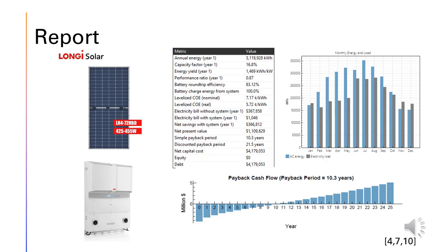From our simulations, we determined that the optimal configuration will be using the LONGi bifacial panels and the 208V ABB inverters. SAM provided us with a report of all the important metrics from our simulation. The LCOE of our proposed system is 7.17 cents per kilowatt hour, while the payback period is 10.3 years. We also used the graphs to ensure the generator power was sufficient for the electricity loads of the Bergeron.